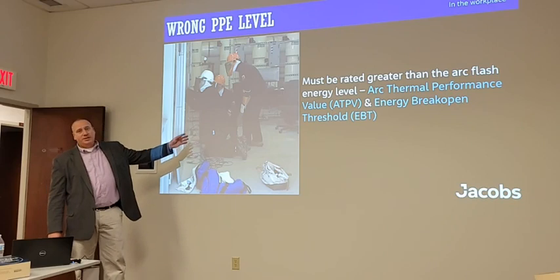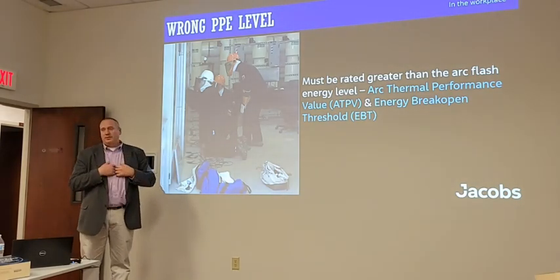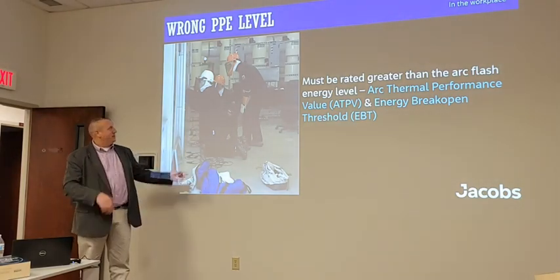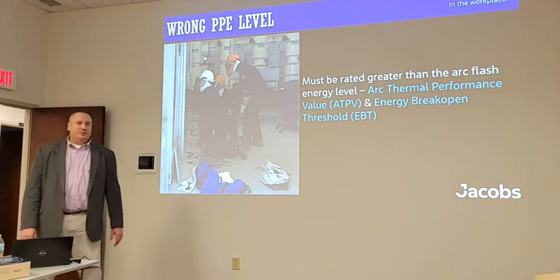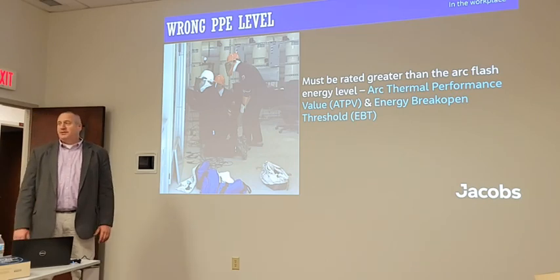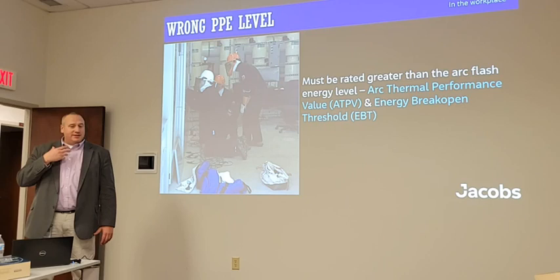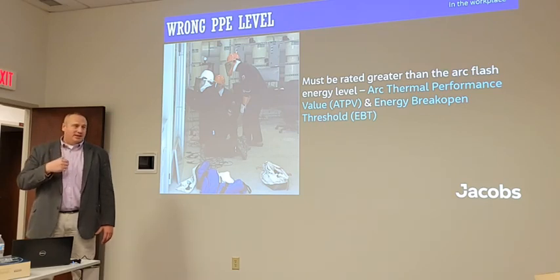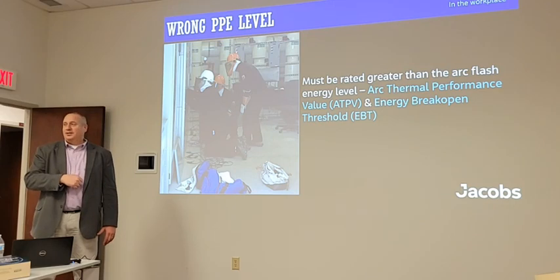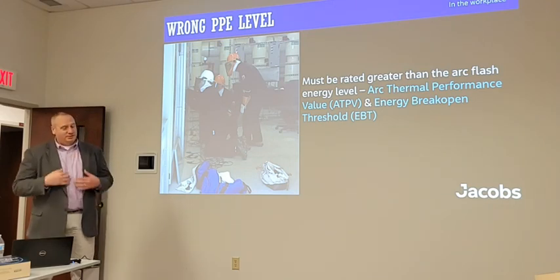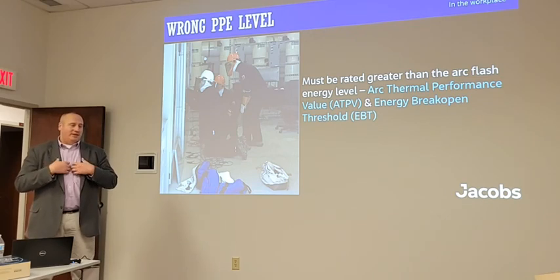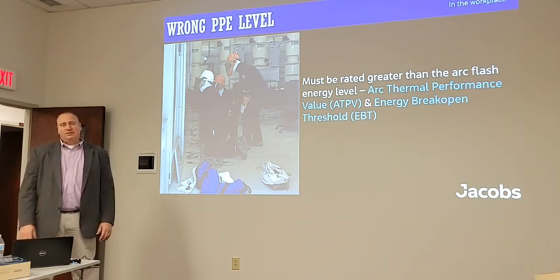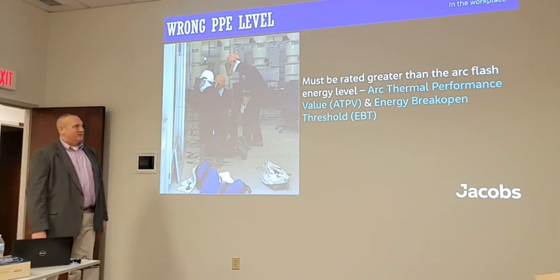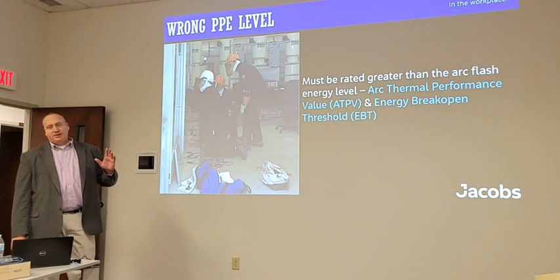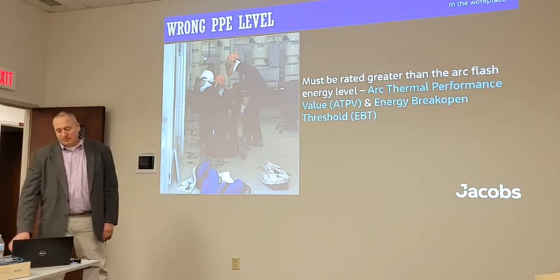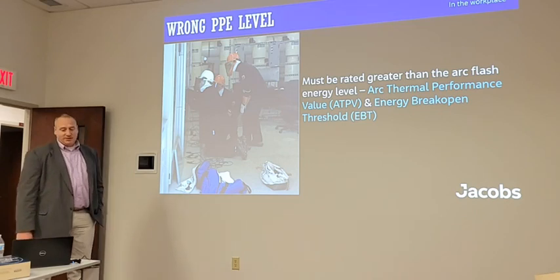If that was to be worn for a 30 calorie arc flash, the Velcro that's in the front may break open, expose whatever's underneath it, which typically is going to be a cotton t-shirt because that's what I prefer to wear under my arc flash PPE. And then that cotton's going to ignite, and the arc flash PPE is self-extinguishing. You can actually take a Bic lighter to a lot of it and hold it there long enough that it'll catch fire, and then you can just work your way through burning holes through it. So if you got a cotton shirt underneath your arc flash PPE and it breaks open and it ignites, then it's no different than just not having your arc flash PPE on anyway. So you want to make sure your outer layer is rated for the energy level that you can be potentially exposed to, or it could be a fatal decision.